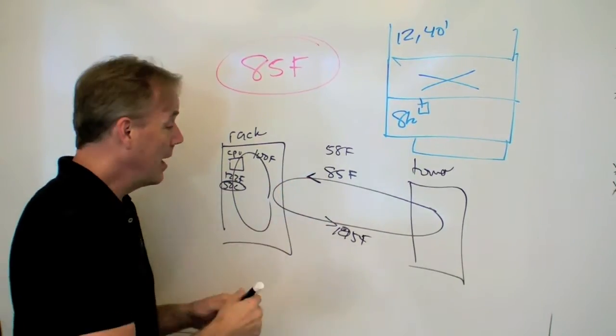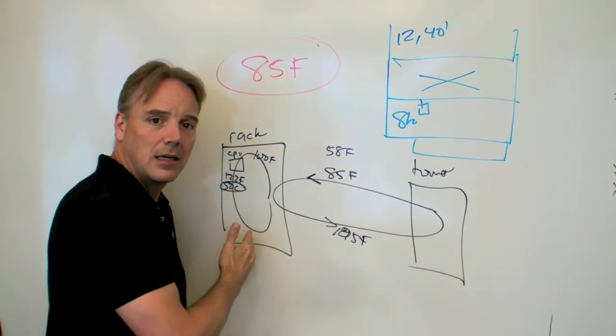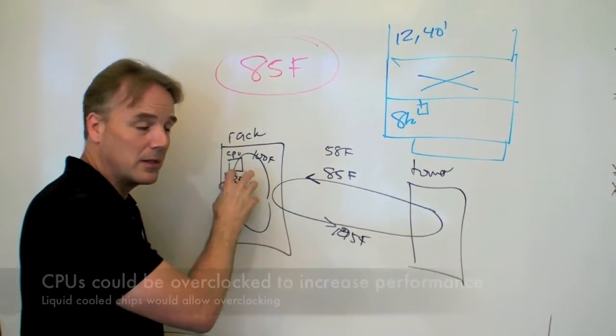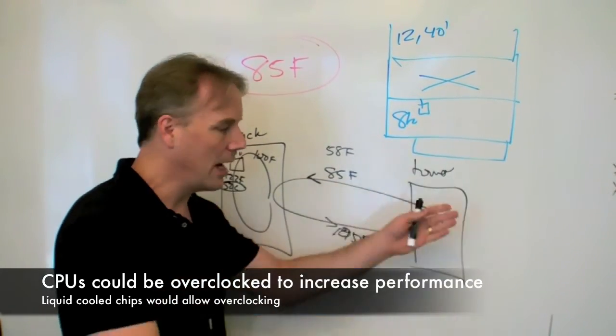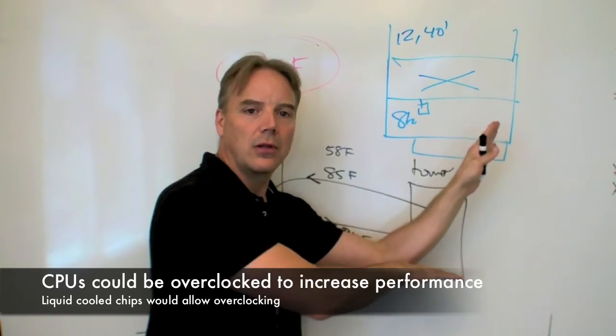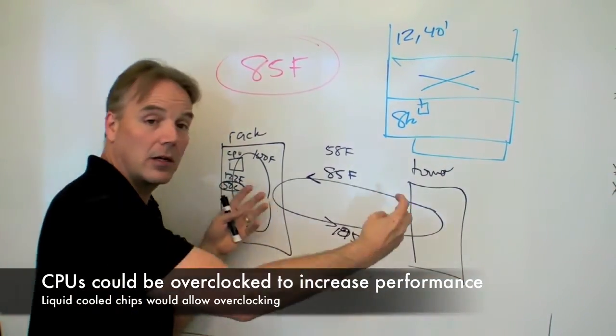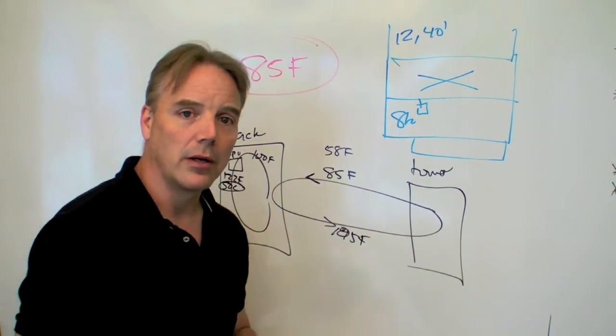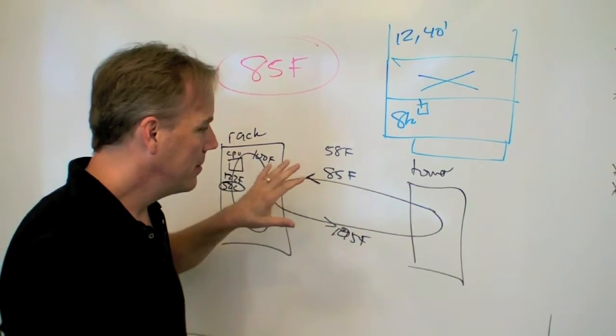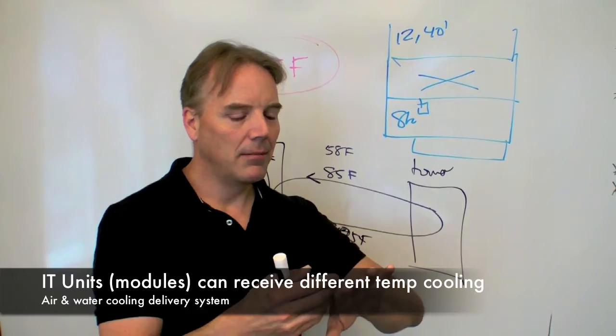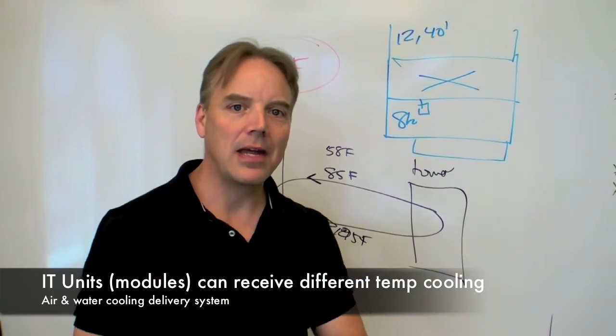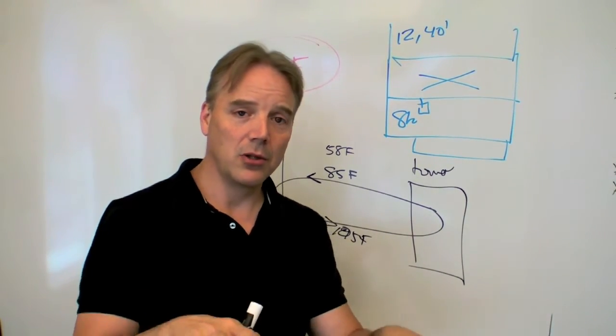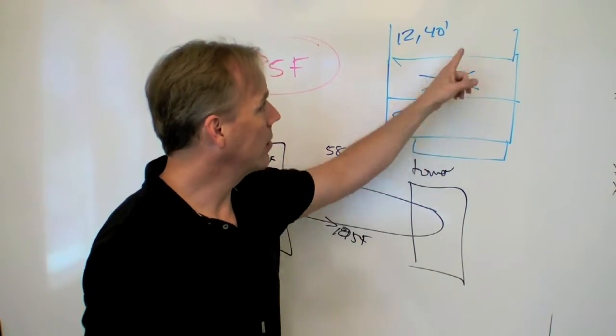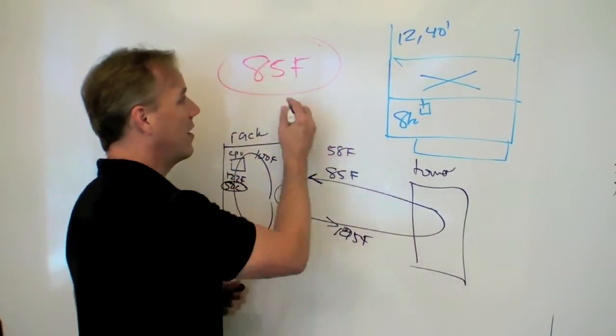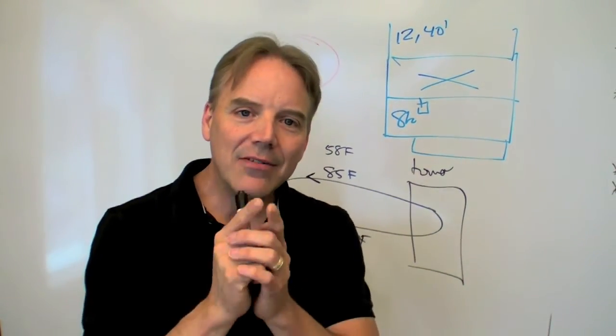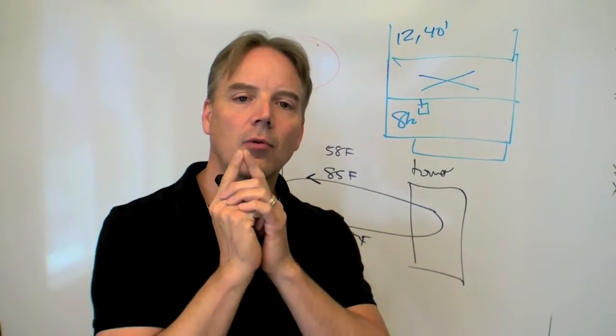But this is a generic solution that I don't really care what's inside the rack or the container or the box, as long as it's going to give me the maximum compute performance to the optimum cooling infrastructure performance. It's not either or, and it's not designing everything to make the facilities look absolutely great without considering the workload itself. It's marrying these two together. So hopefully this gives you a little more clarity on what we're trying to accomplish. But what I want you to think about is you should be able to come up with a design that makes each rack or each container or each module independent. So a solution that can scale to be able to do multiple water temps, high temp air solutions, most likely in here or just going through containers or boxes on the roof, that can go for that 85 degree Fahrenheit in Phoenix, Arizona. Because the key for me is the industry is seeing what's going on, real project, and we're all learning at the same time.